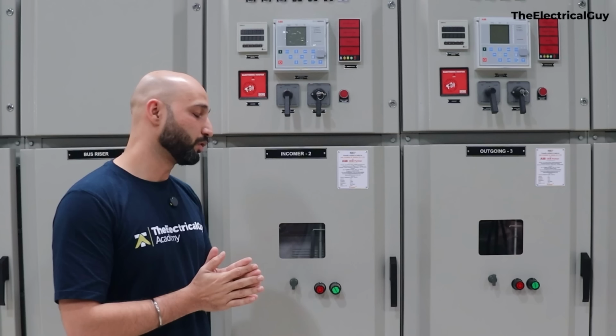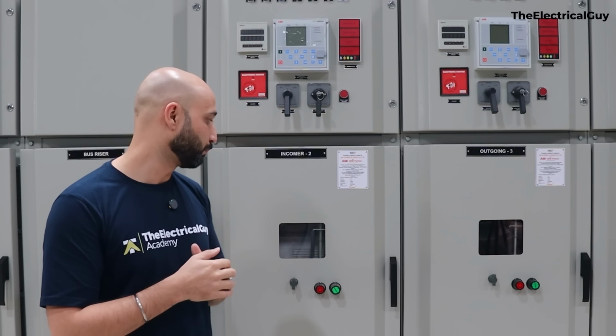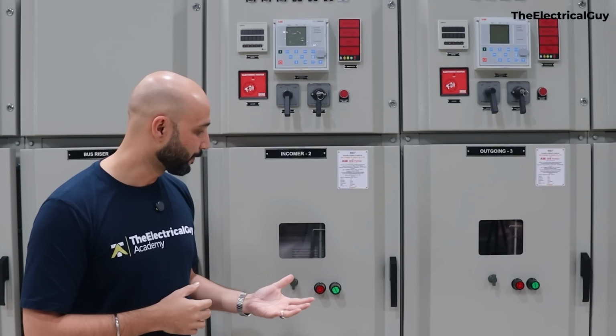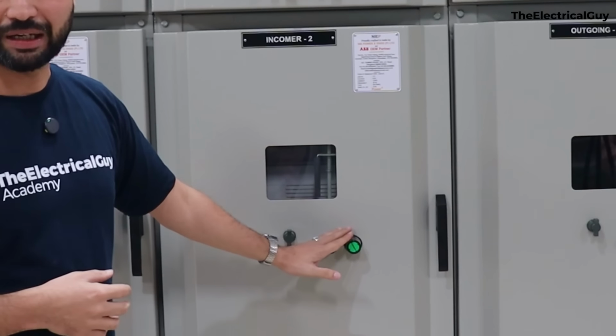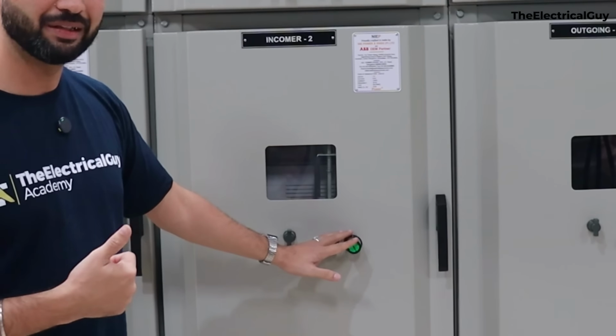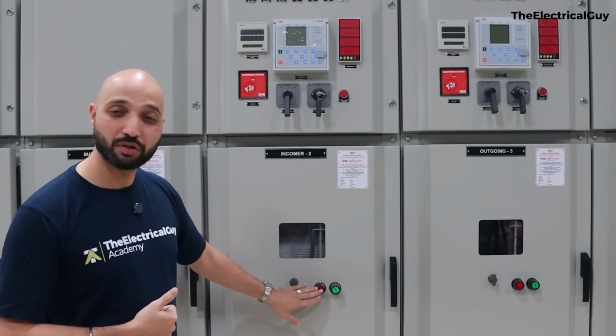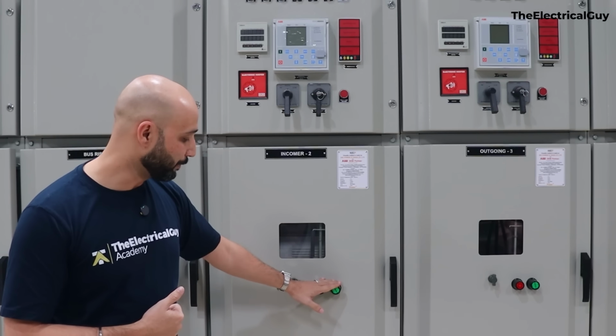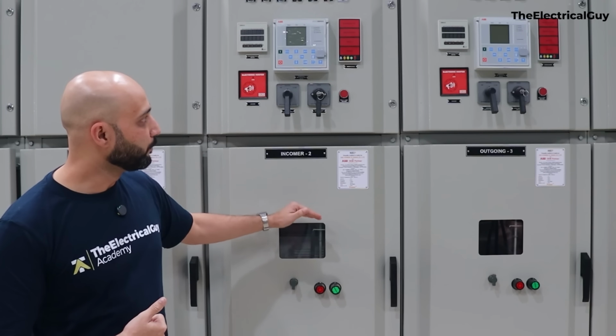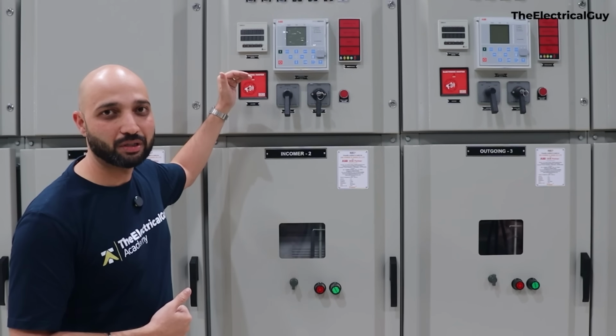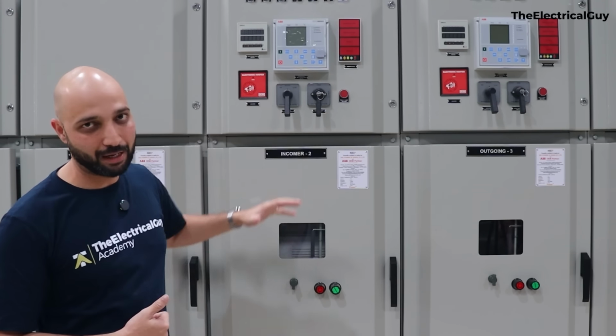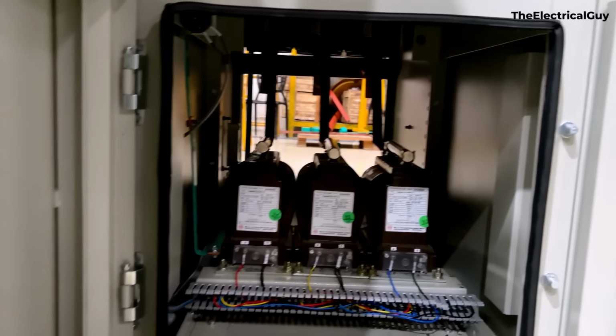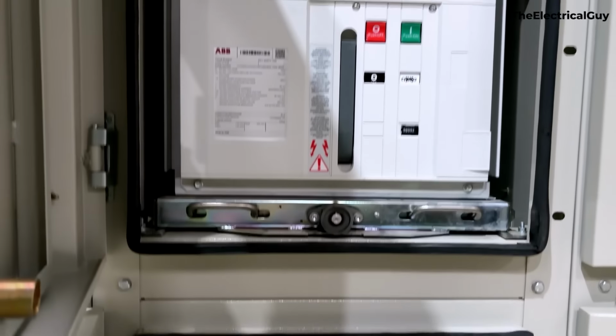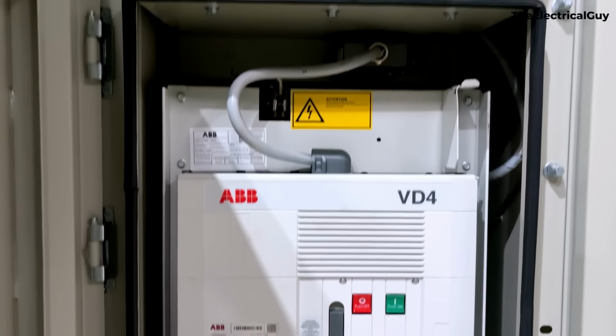You can see the different switches here. We have two switches to push on, push off. Then there are emergency trips. So in case something goes wrong, you need to emergency trip the breaker. We have the switches here. This is the emergency trip. And now we move towards the next part, which is the low voltage side of the panel. Now these are different chambers, as we can call them. The bottom chamber can be called the cable chamber, because we are accepting the cables there.